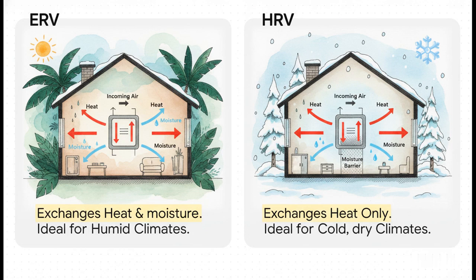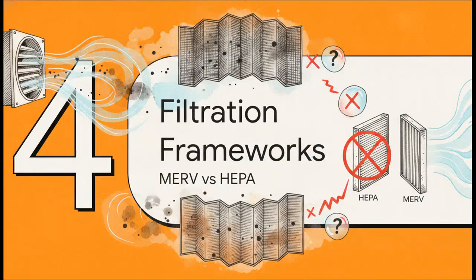Conversely, a heat recovery ventilator, the HRV, transfers heat only. HRVs are strictly for very cold, dry climates, zones 6 through 8, where maximizing heat recovery is the top priority over humidity control. Choose the wrong system for your climate zone, and you will actively create humidity problems that compromise the entire building envelope. Module 4, Filtration Frameworks, MERV versus HEPA.